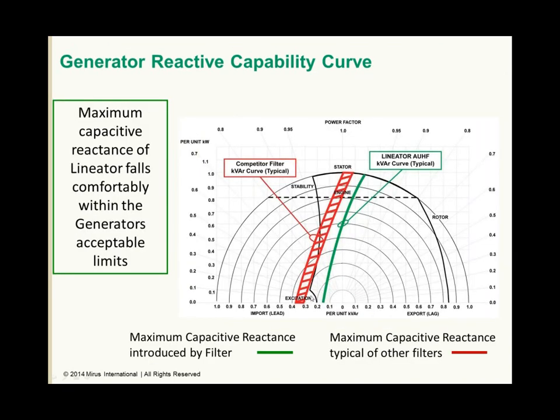Why is that a problem? Well, when you're in the 35 to 40% range, you end up being outside the generator reactive capability curve. So this is a typical generator reactive capability curve. Here again we show reactive power leading on the left side, lagging on the right side, loading on the y-axis. The various power factors of the loads are radial curves coming out from the center of that graph. As long as the load on the generator is within this envelope, the generator can handle the reactive power without incident. So we can see that for lagging loads or inductive loads, generators can easily handle very low power factors, very high levels of reactive power.